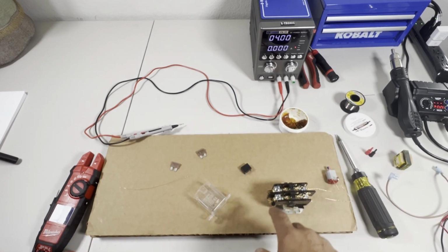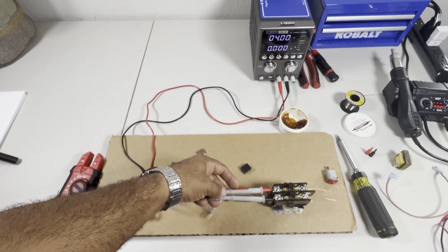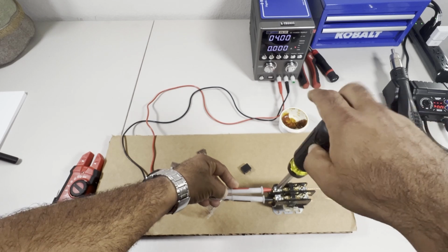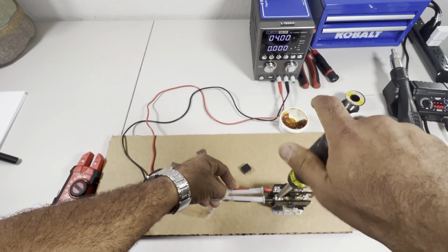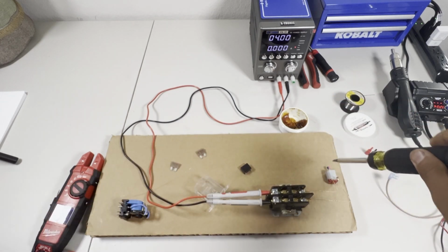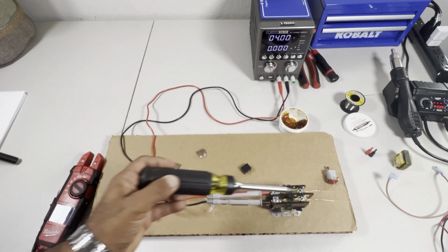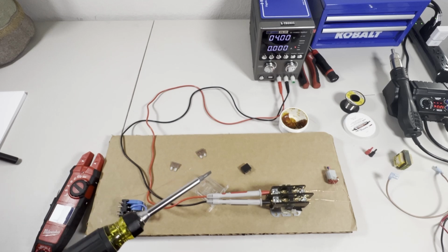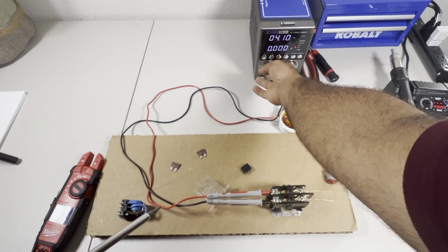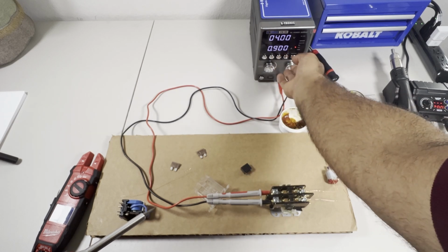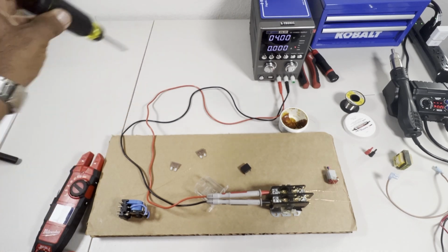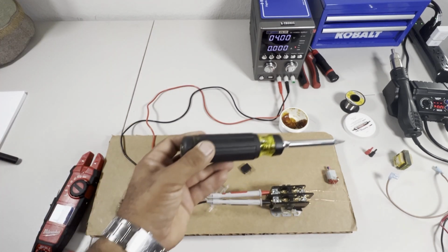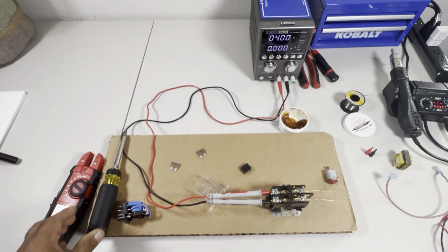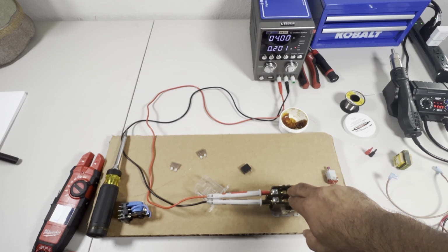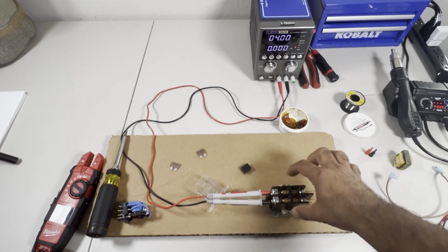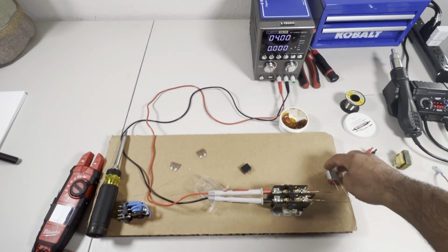That's what they do. How it works is the main power is coming in to the input of the relay. Some of the relays are a little different in design, but they are all doing the same thing. And your load is going to be on the outgoing side of the relay. Most relays do not have a polarity, so it really doesn't matter. And when you have the power and everything ready, and the control board is calling for whatever component to come on, it could be a compressor, a motor, a blower motor, whatever the case may be, that relay closes, and here we go, that motor is running. And as soon as the control side, which is over here, is disconnected, that load is going to stop.